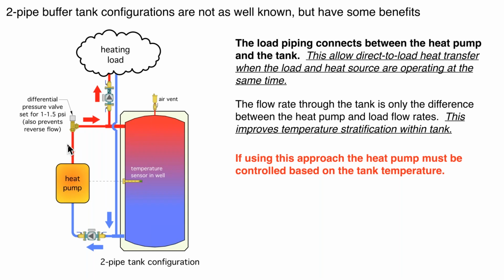But one of the ways that we've found works well to prevent that is to put in what's called a differential pressure valve. And these are available from several manufacturers, and set the spring in there. You just adjust the knob for a forward opening pressure of anywhere from 1 to 1.5 PSI. And that's a strong enough spring pressure to prevent that flow from going back this way when the heat pump is off, all right? And it also replaces the need for the check valve. So you can think of it in effect as an adjustable check valve, or adjustable spring check valve, to get a little bit more differential pressure.